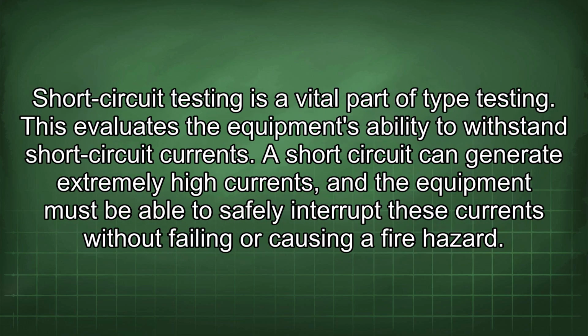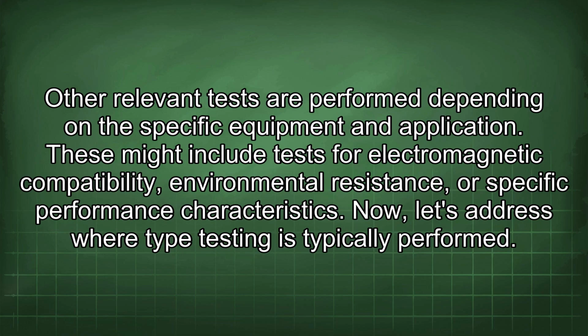Short-circuit testing is a vital part of type testing. This evaluates the equipment's ability to withstand short-circuit currents. A short circuit can generate extremely high currents, and the equipment must be able to safely interrupt these currents without failing or causing a fire hazard. Other relevant tests are performed depending on the specific equipment and application. These might include tests for electromagnetic compatibility, environmental resistance, or specific performance characteristics.